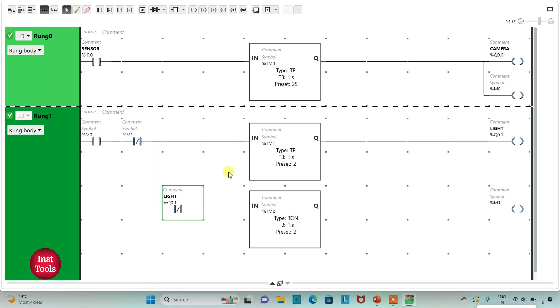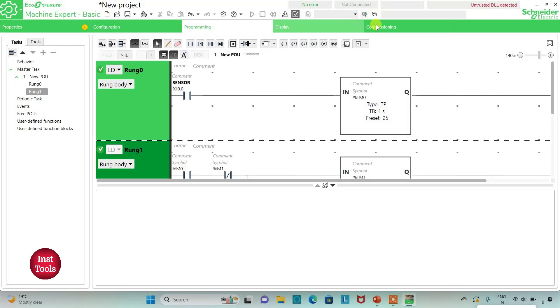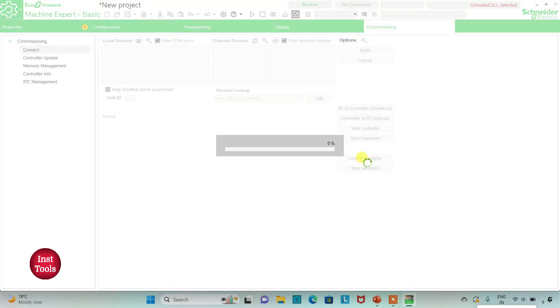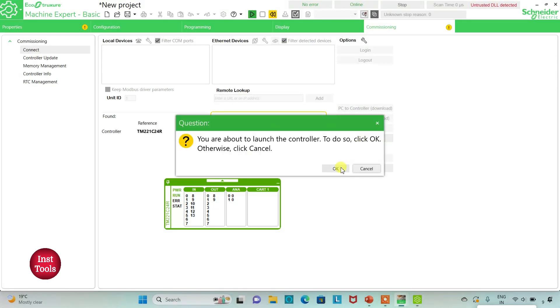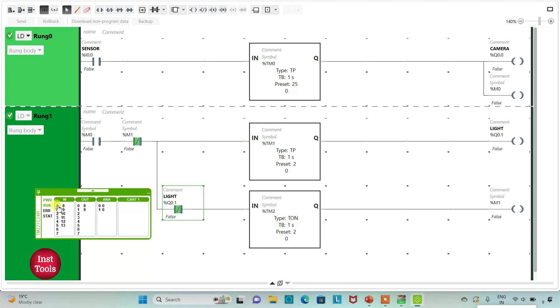As a result, the light will again turn on for 2 seconds. I will exit full screen mode, compile the program, then go to Commissioning and launch the simulator. I will start the controller and go to the Programming tab in full screen mode. When the motion is detected, the sensor gets activated, the camera turns on for 25 seconds, and in those 25 seconds the light will blink with an interval of 2 seconds.